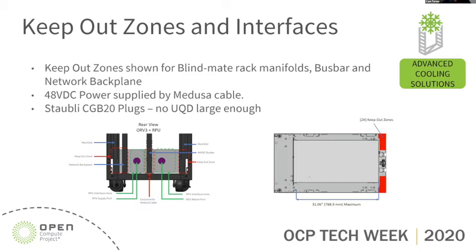And finally, on the liquid interface, we're utilizing Staubli's CGB20 plugs, as there is no large enough UQD to support the flow rate required for an entire rack. And this is something that will be investigated moving forward with the community as a whole, is standardizing on a larger quick disconnect.